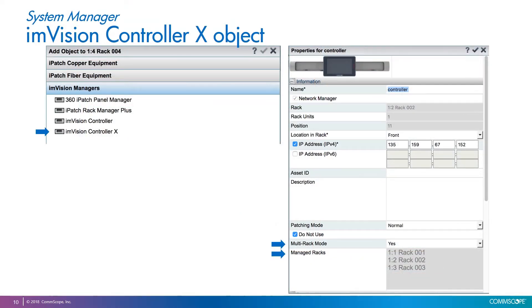Now let's see how all this is represented in System Manager software. A new imVision Controller X object is now available in the list of imVision Managers that you can add to racks. The properties of this object include a setting called multi-rack mode, which can be set to yes or no. This setting can be manually configured or can also be set automatically by System Manager if, during a synchronization, it finds that the controller is connected to more than one panel bus. There is also a new field that shows the racks this Controller X manages — in this case racks 1, 2, and 3.